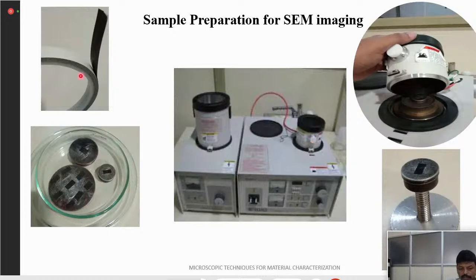So we are just putting our sample over this conductive tape on the stub, and we'll be directly analyzing the sample. But if you are going with non-conductive samples like polymers and some other biological samples, we'll paste the material we want to observe on the carbon tape, and we'll go for gold sputtering. And this is known as the stub holder, and we'll be placing the stub over the stub holder, and we'll go for analysis. That is the usual procedure we are doing here.